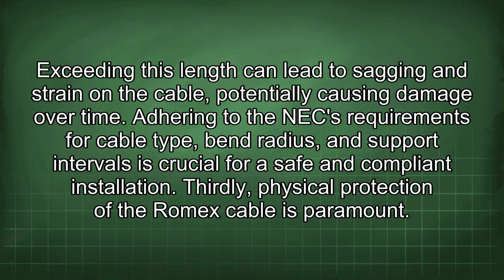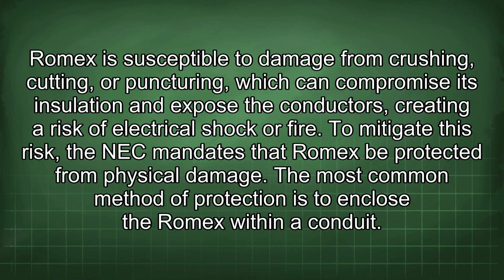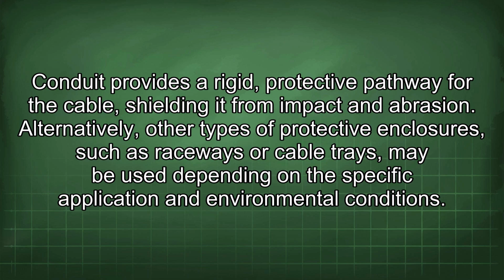Adhering to the NEC requirements for cable type, bend radius, and support intervals is crucial for a safe and compliant installation. Thirdly, physical protection of the Romex cable is paramount. Romex is susceptible to damage from crushing, cutting, or puncturing, which can compromise its insulation and expose the conductors, creating a risk of electrical shock or fire. To mitigate this risk, the NEC mandates that Romex be protected from physical damage. The most common method of protection is to enclose the Romex within a conduit. Conduit provides a rigid, protective pathway for the cable, shielding it from impact and abrasion. Alternatively, other types of protective enclosures, such as raceways or cable trays, may be used depending on the specific application and environmental conditions.